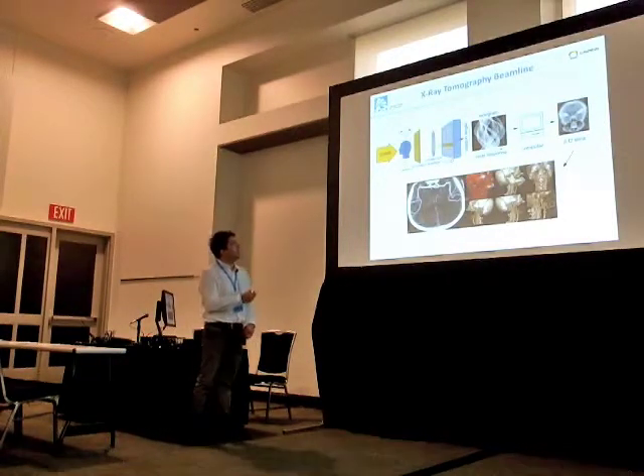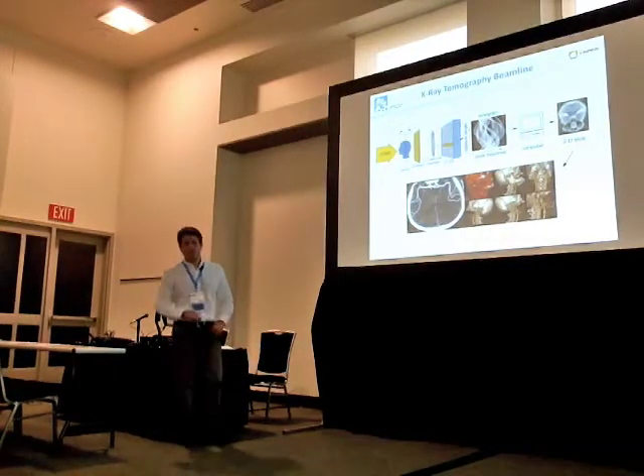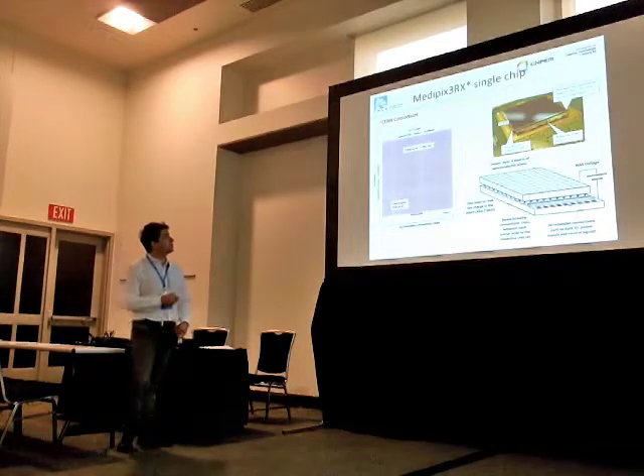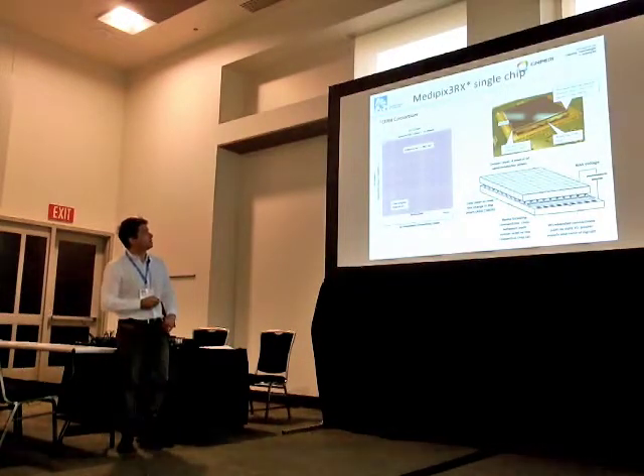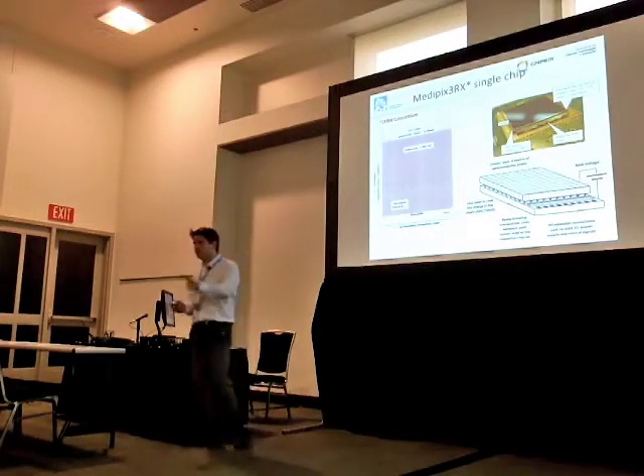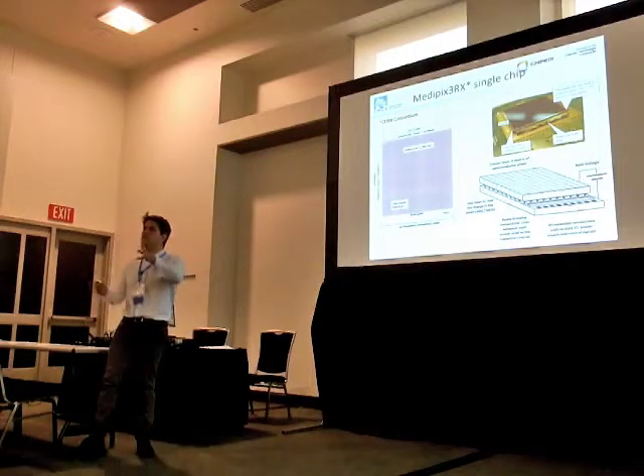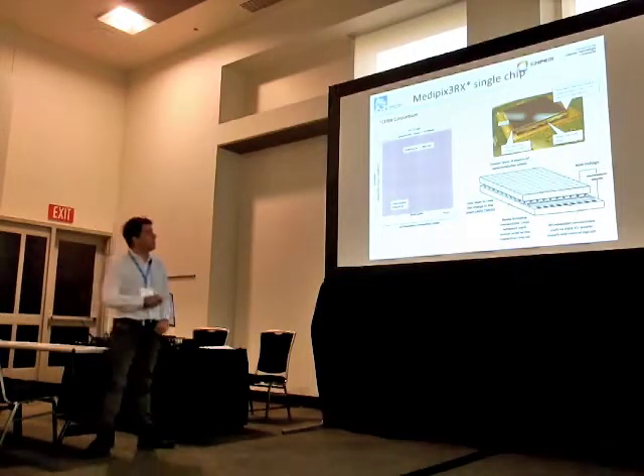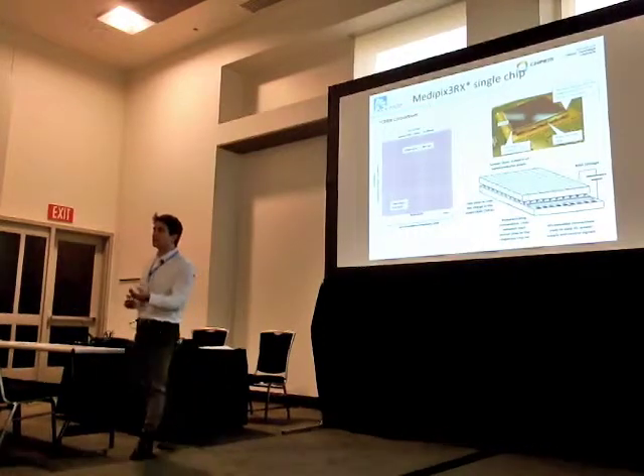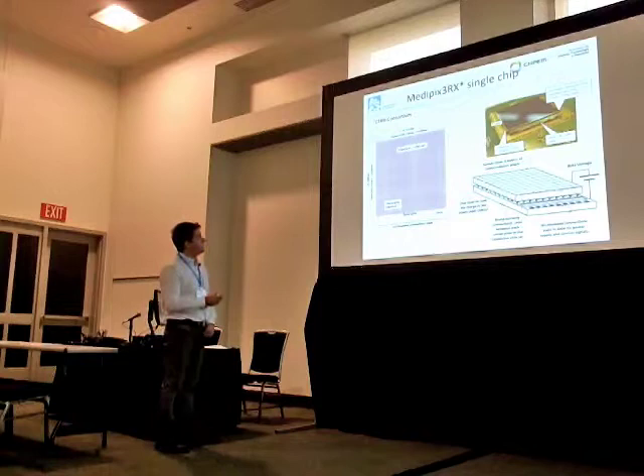Now, going to the detector system of this kind of experiment, we have a project to build our own detectors. So we started collaborating in a CERN consortium. We are part of it. It's called Medipix. Basically, the simplest way of converting X-rays to digital information, you convert them to visible light, with a scintillator, and then you use a standard CCD. But the best way is if you can convert directly X-rays into electrical signals and digitalize them.